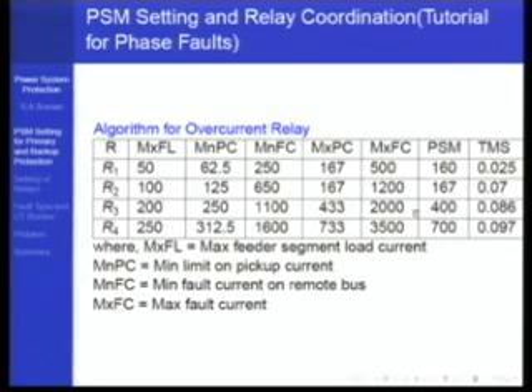I have maximum fault current is 2000. We have decided that we will try a pickup value of 400 amperes. And similarly for R4, let me not repeat that calculation. 250 into 1.25 is 312.5, and minimum fault current for its own section is 1600, but for backup the minimum fault current is 1100. So 1100 into 2 by 3, which is 733. So therefore the maximum pickup current can be 733, minimum pickup current can be 312.